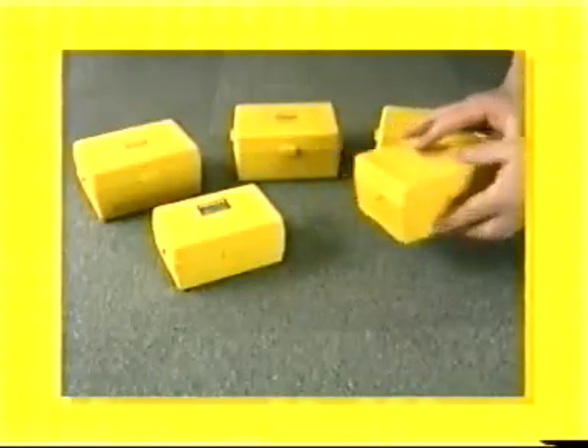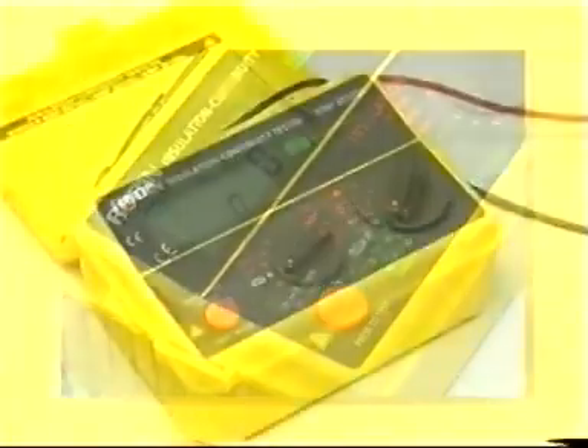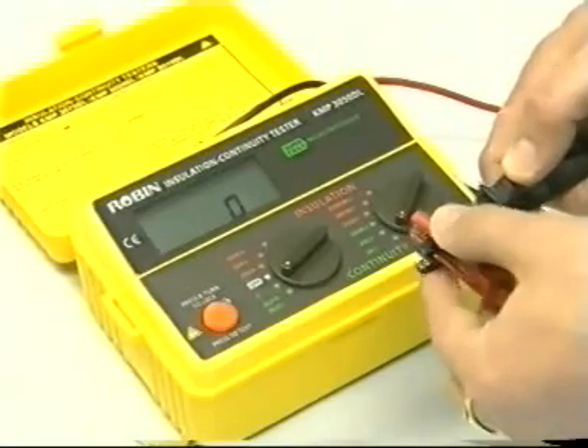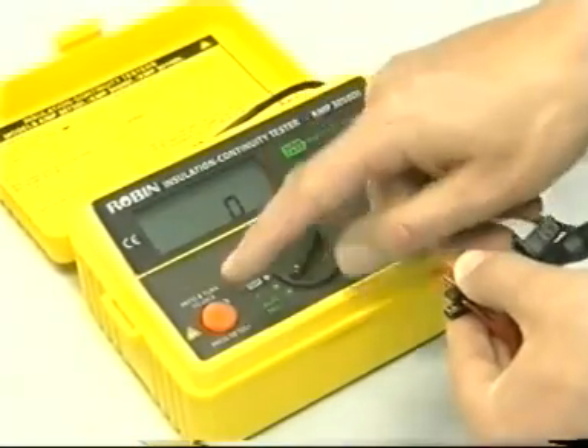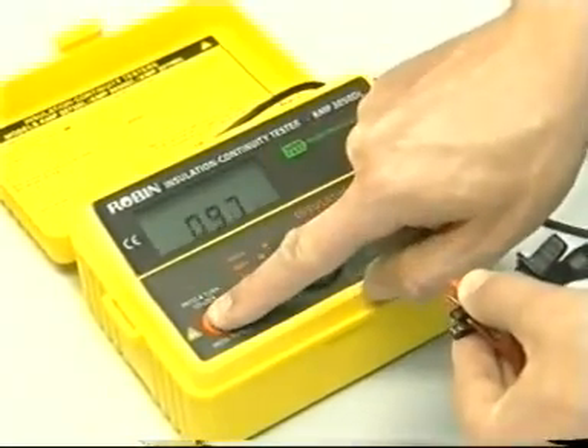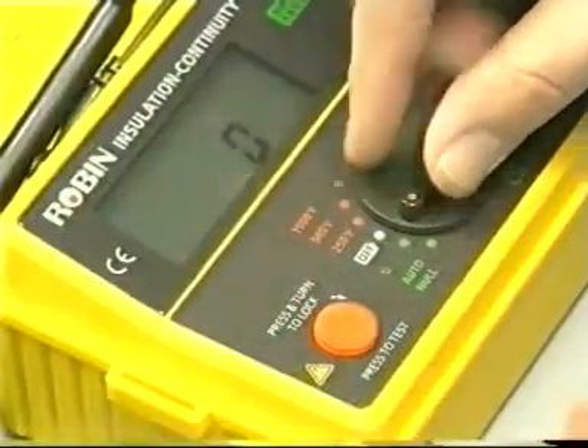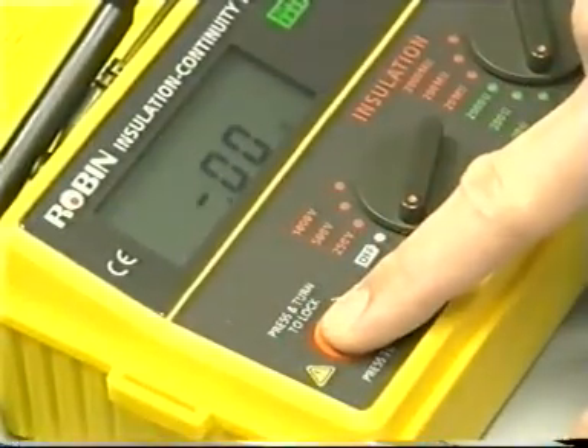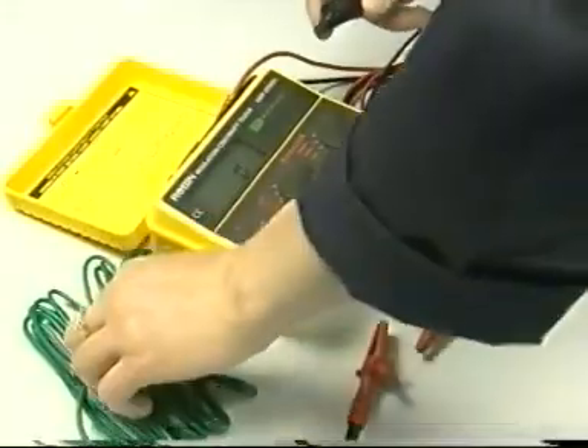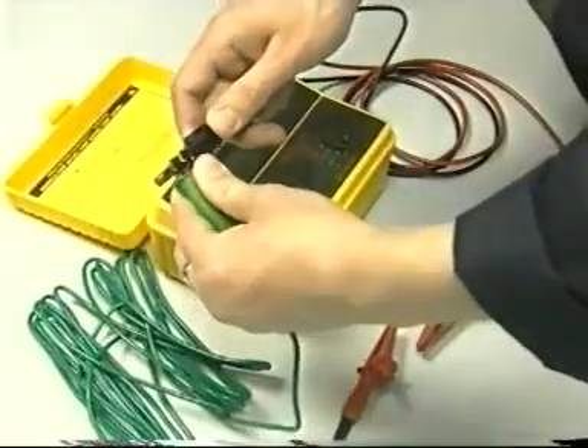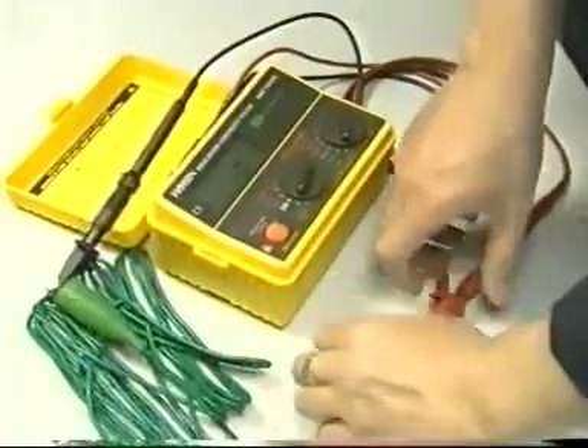Correct test equipment must be selected and prepared for use. As low conductor resistance is to be measured, the test leads resistance, which will be in the test circuit, must be compensated for prior to testing. If a wander lead is necessary to extend the short instrument test leads, this must be included in the nulling process.